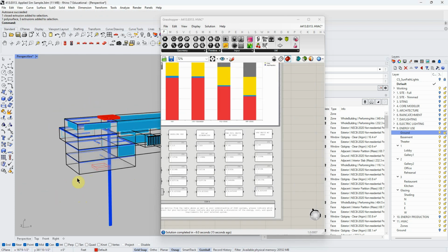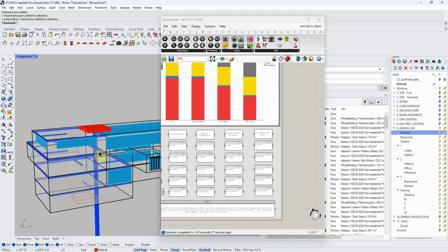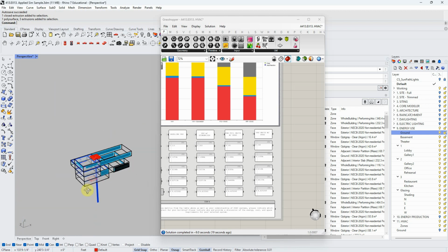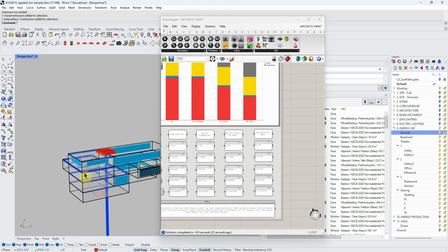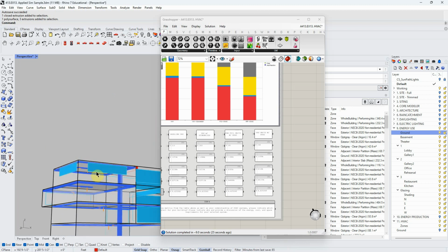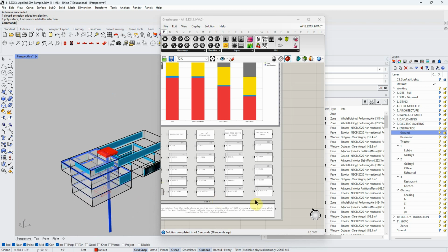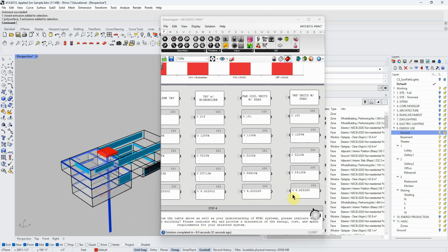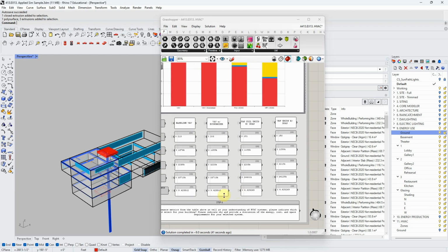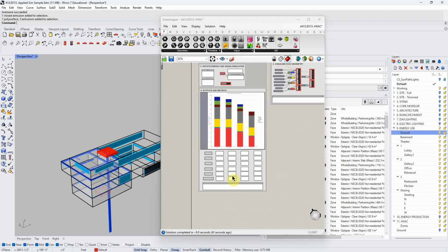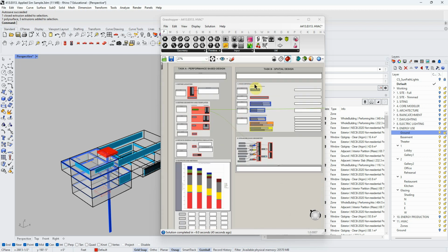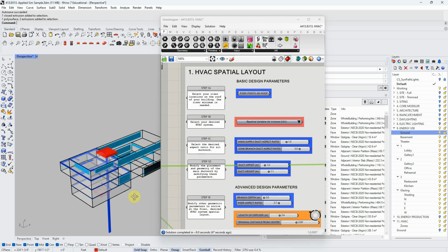So I paused and just went and reran it because it was driving me crazy. I got this to work much better. This looks more like a sensible HVAC layout for both the basement and this side of the building. But what I was getting at is that you see how these two, the VRF and the DOAS units, where you have a big unit on the roof that's also doing fresh air, are much smaller. The ducting is smaller, and so the equipment is smaller. And that's really what we're modeling here is the size.